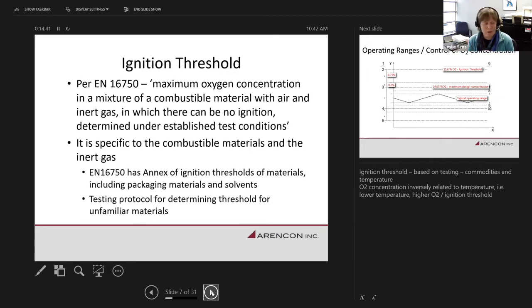The pass-fail is quite similar to the cone calorimeter test, where we're looking at a reduction in the material. So we're not seeing that we've lost any of the combustible materials through the test. So the ignition threshold is very specific to the materials in this space and the concentration of the gas. That standard does have an annex that has ignition thresholds for some typical materials, really based on packaging materials, some of the plastics that you see in packaging materials, the cellulose materials, the cardboards, the paper, the wrapping.